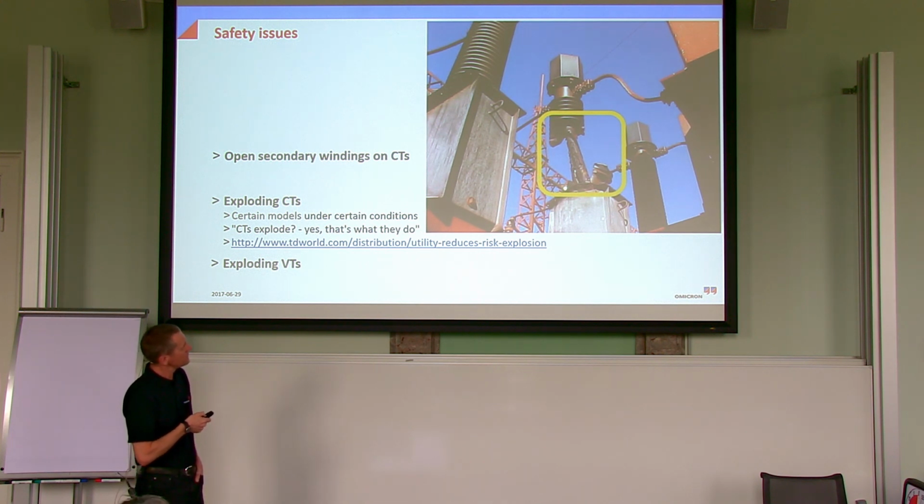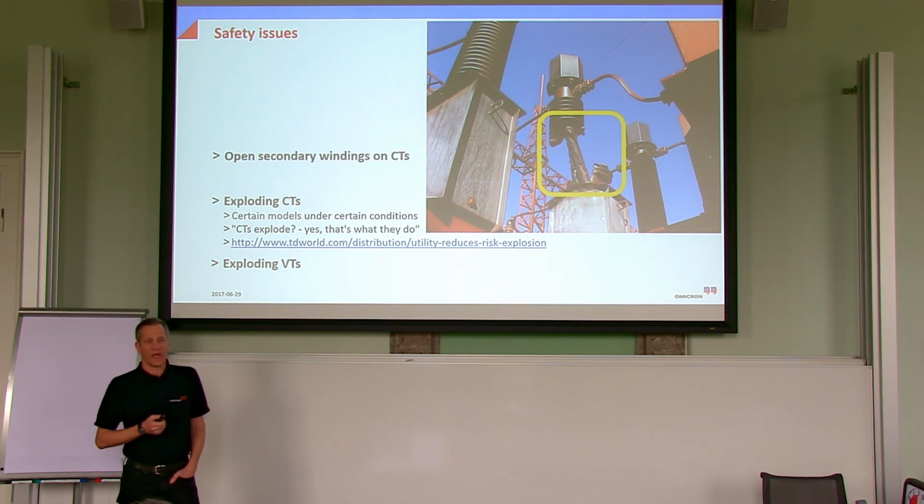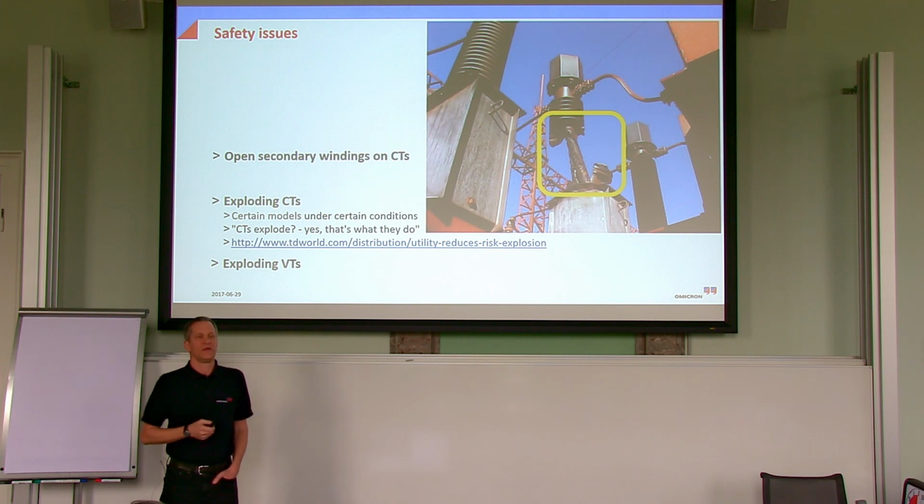And if you look here, here was once an isolator. Yeah? And the pieces that went off here are like pieces of a hand grenade. And it depends on the environmental conditions and on the model and make of such isolators and CTs. It is really, really very, very dangerous. And in some places, this is the reason to go away from conventional sensors.